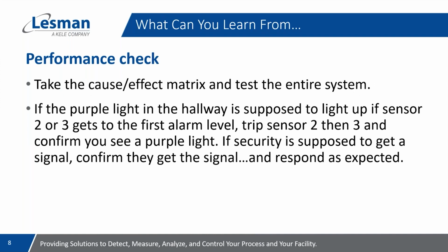This brings us to the crux of today's conversation, the performance check. As mentioned before, there's no specific definition of what this means. So clearly identifying the scope and the steps required is critical, but I look at it as a check from tip to tail. You check everything from detector performance to the alarm outputs and their functions, right down to the employee behaviors that you want and expect. It is the hardest part to plan and organize, but it's the only way I know of to confirm the system and the people are functioning as originally designed. I have some examples of where these maintenance activities can teach you things you might not expect.